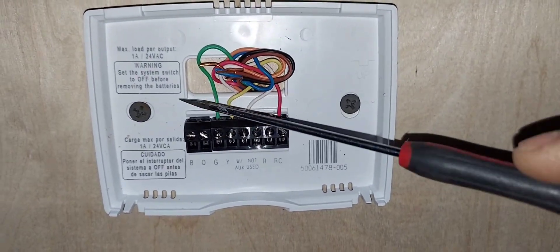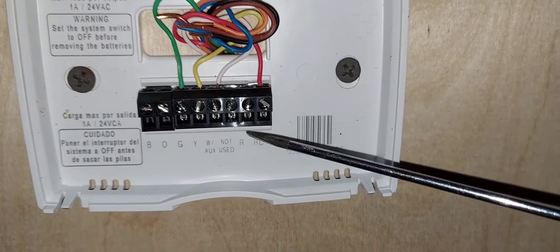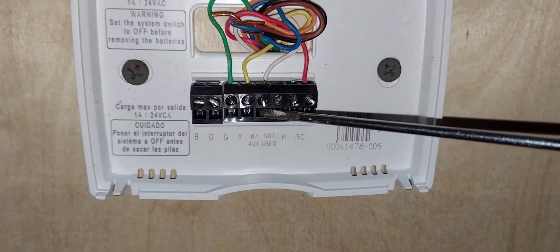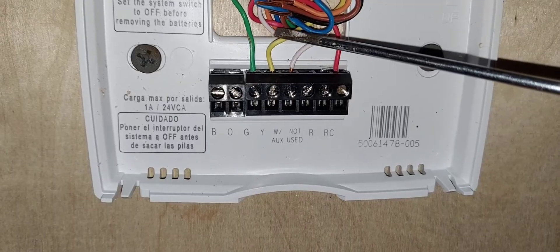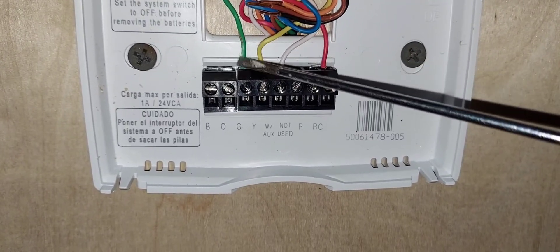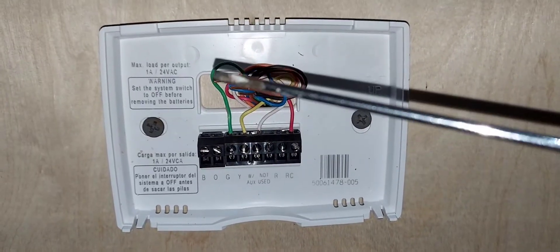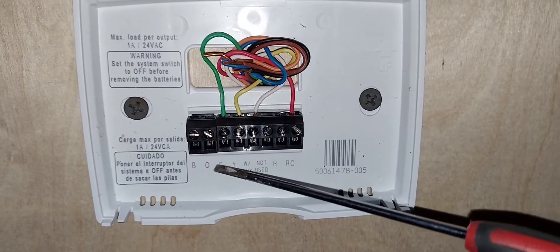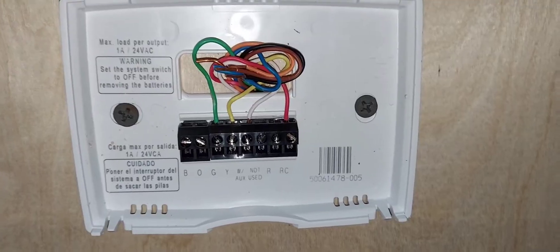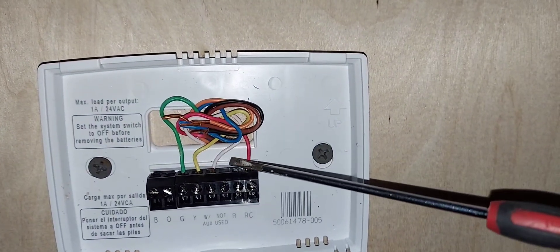These are the typical colors an HVAC technician or contractor will use when available. R or RC is red — that's your power. W is for heating — white wire. Y is for cooling — yellow wire. G is for your fan — green wire. Remember, the colors are arbitrary; do whatever you want with colors, just make sure the wire on G at the thermostat corresponds to G at your HVAC heating or cooling equipment.